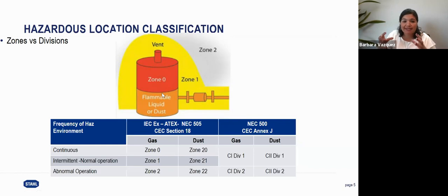A little bit outside that tank, we have a zone 1, where in normal operations you will have the presence of explosive atmosphere. And farther away, zone 2 will be abnormal operations, where you might have a presence of explosive atmosphere for a short period of time. So when we classify on zones, we have zone 0, zone 1, zone 2 for gas, and zone 20, zone 21, zone 22 for dust. The lower the number, the higher the risk.